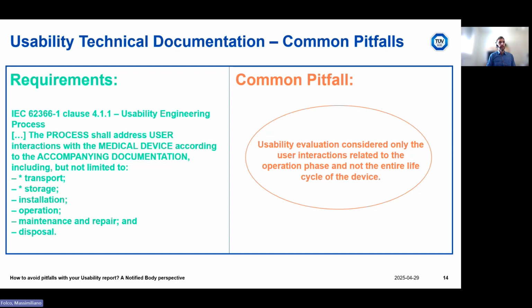For example, we can have a more complicated life cycle for active medical devices, where you have transport, storage, installation, operation, all those phases. A less complicated life cycle for single-use non-active medical devices, where you do not have installation, maintenance and repair. Other cases can be, for example, reusable medical devices, where there are a lot of operations that have to be done between one user and another for cleaning, disinfecting, and sterilizing the device, and maybe also for maintenance and repair of the device, for example, mounting the device.